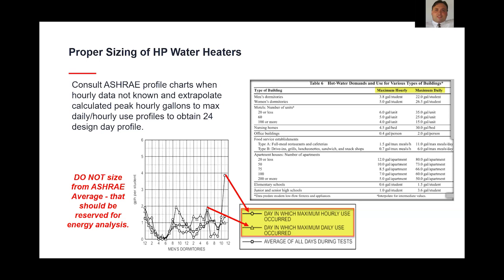So again, they know what the peaks are, and they can take that data and apply it to these ASHRAE profiles. Again, instead of using the average data that ASHRAE publishes, we would be looking at one of these design conditions. So they have a couple. They've got days in which the maximum hourly use occurs, and then days in which the maximum daily use occurs. And so again, these are dynamic effects because they impact how quickly storage is depleted and how long those water heaters run. And then you can extrapolate those peaks using these profiles.